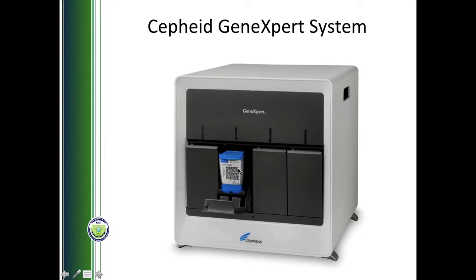Now the system itself will provide the thermal modulation, temperature up and down, needed for the PCR reaction. The system itself will detect the fluorescence, which is released as a part of the qPCR reaction, and the entire system can then be attached to a PC or laptop in order to export the final result. So this is known as the Cepheid GeneXpert system.